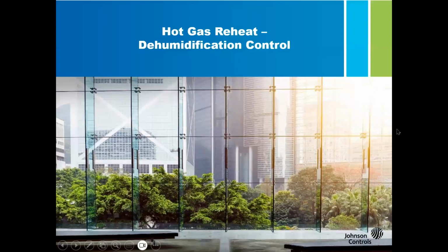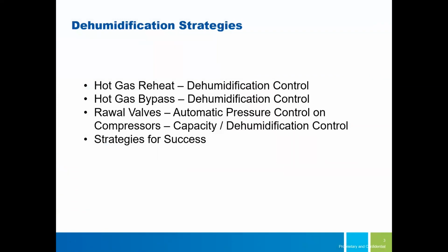So our focus today is, I want to cover 3 ways that I know are usually successful strategies to do dehumidification. You've got the option for hot gas reheat, and we want to discuss how that does dehumidification. We're going to talk about hot gas bypass, which is a kind of indirect way of doing dehumidification. And then you've got Rawal valve, which is, we'll call it, a tricked out version of doing capacity and dehumidification control. And then at the end of this, we want to recap and discuss strategies that we think will lead you to success. Next slide.